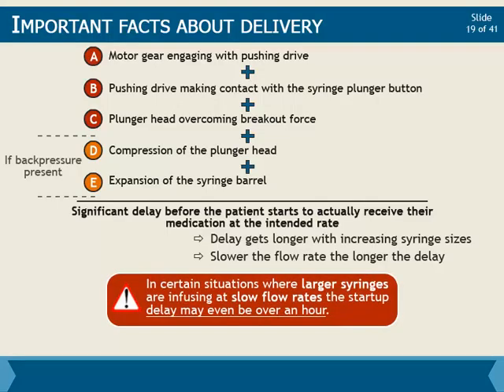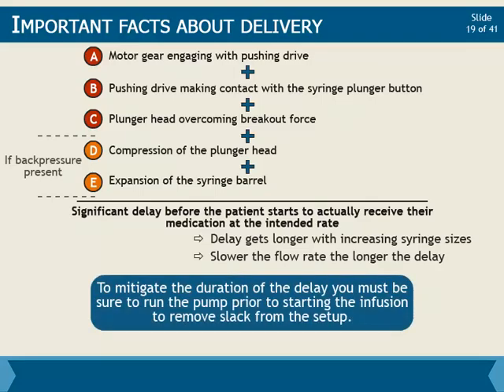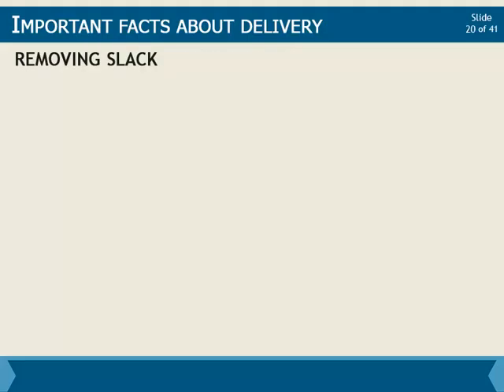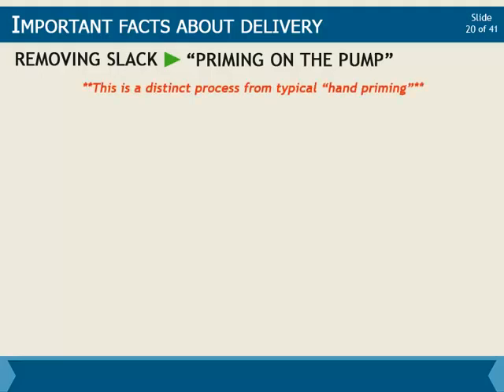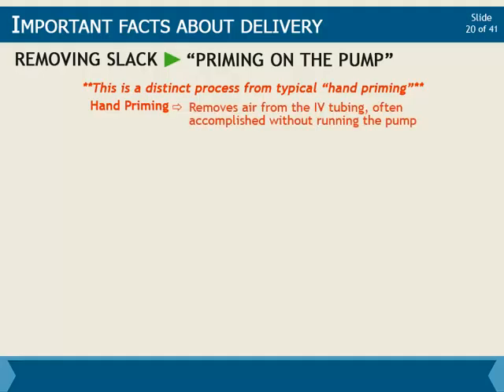In certain situations where larger syringes are infusing at slow flow rates, the startup delay may even be over an hour. To mitigate the duration of the delay, you must be sure to run the pump prior to starting the infusion to remove slack from the setup. This process of removing slack prior to the start of medication administration is primarily called priming on the pump, and sometimes purging the setup. Please note that this should be considered a distinct process from typical hand priming. Hand priming is done for the purpose of removing air from the IV tubing and is often accomplished without running the pump and will therefore not remove slack.